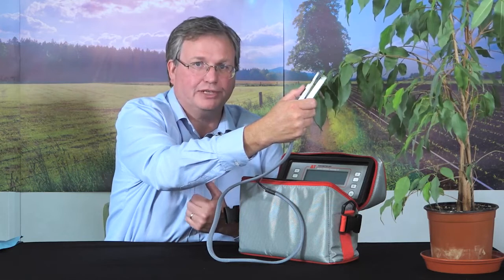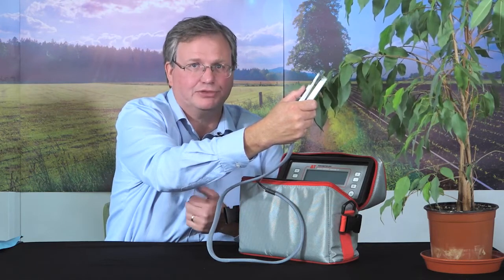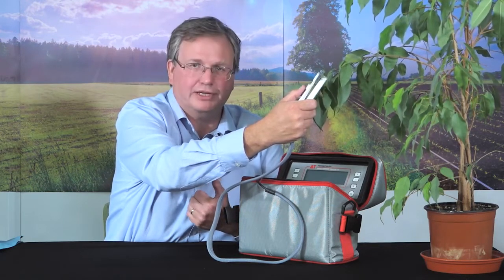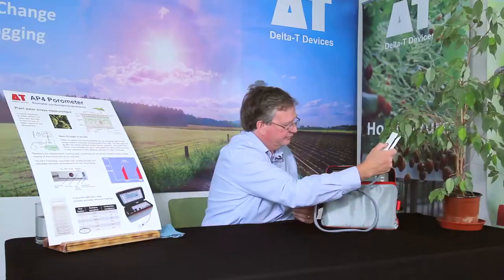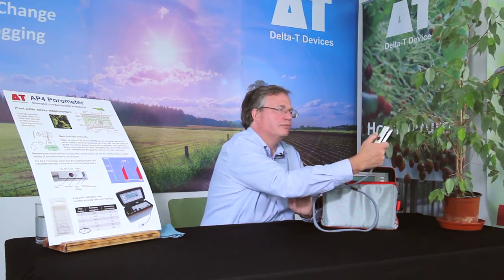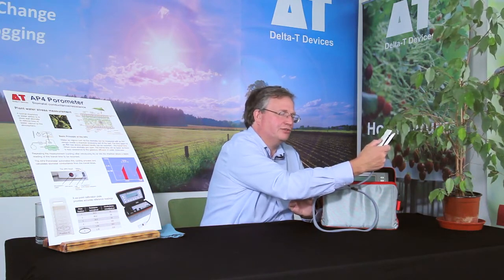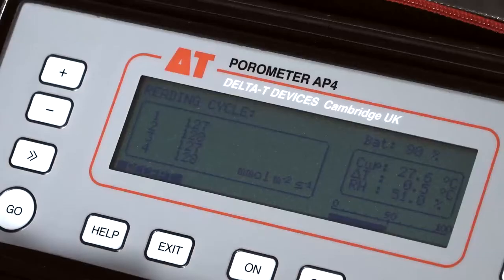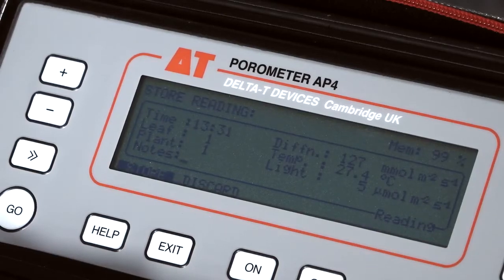When we have two readings within 2% of each other, we'll hear an audible double beep. If you want to, using this in the field, you can do everything just with the red button and the audible signs. You can press the red button to start the reading, listen for the double beep, press the red button to accept, and then again to store the reading. We've got the double beep then, so we'll accept this value.